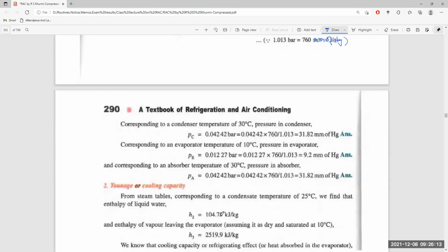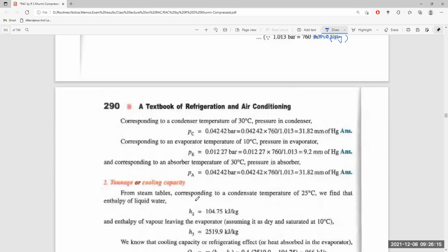Now, tonnage or cooling capacity. From steam tables, corresponding to a temperature of 25 degrees centigrade, we know the enthalpy of the liquid water H2 is 104.75. The enthalpy of the vapor leaving the evaporator, assuming dry saturated at 10 degrees centigrade, is 2519 kJ per kg. This is all available from the steam table.